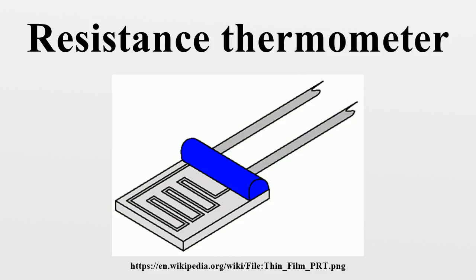Disadvantages of this type are that they are not as stable as their wire wound or coiled counterparts. They also can only be used over a limited temperature range due to the different expansion rates of the substrate and resistive deposited, giving the strain gauge effect that can be seen in the resistive temperature coefficient. These elements work with temperatures to 300 degrees Celsius without further packaging but can operate up to 600 degrees Celsius when suitably encapsulated in glass or ceramic. Nowadays there are special high-temperature RTD elements which can be used up to 900 degrees Celsius with the right encapsulation.